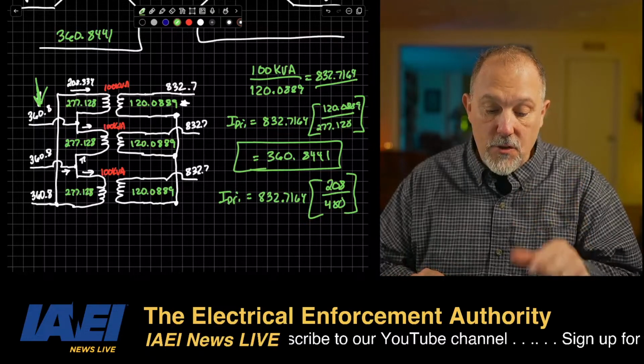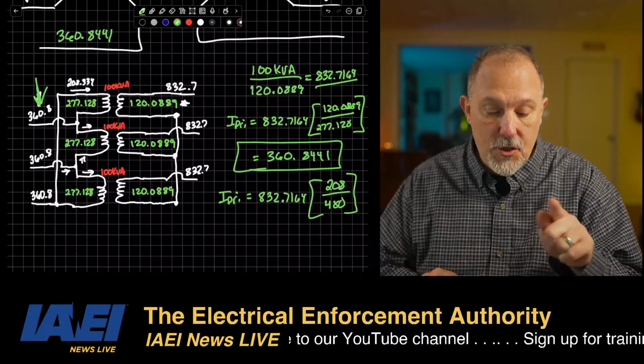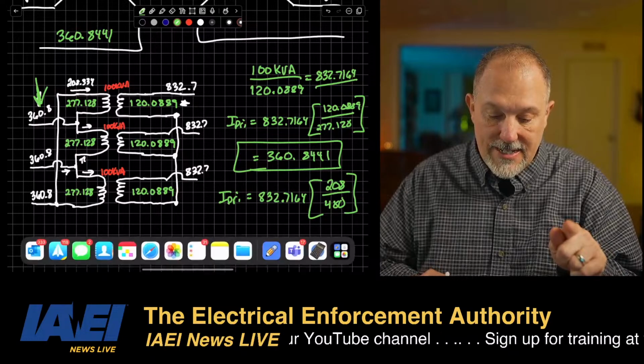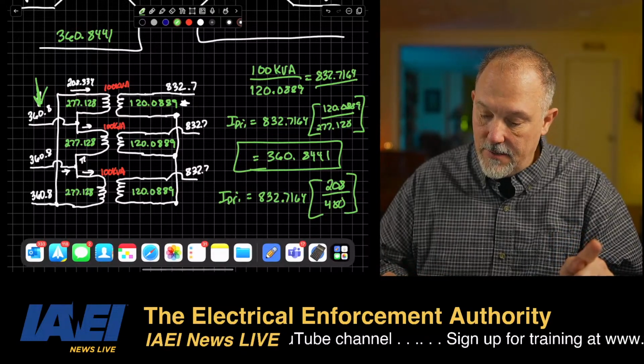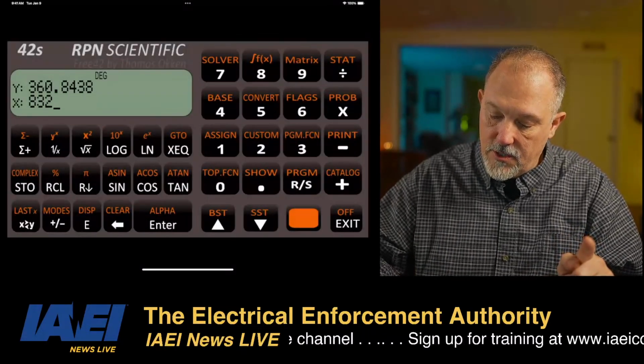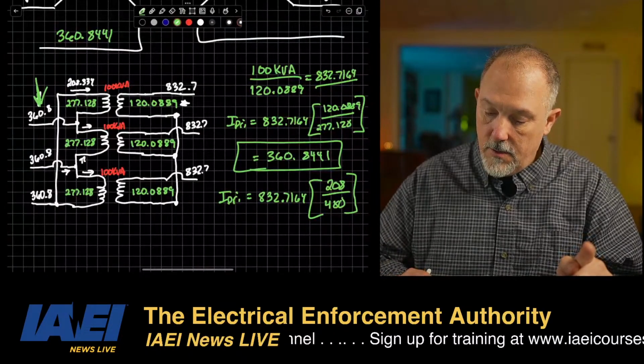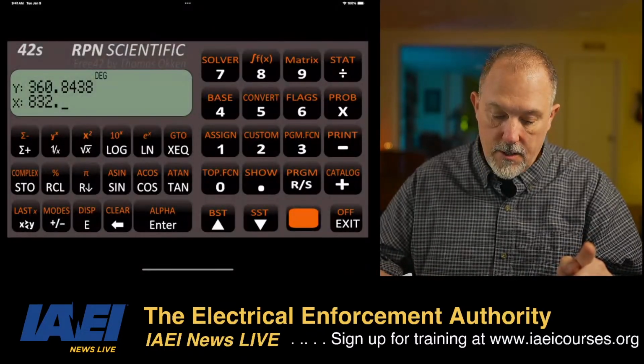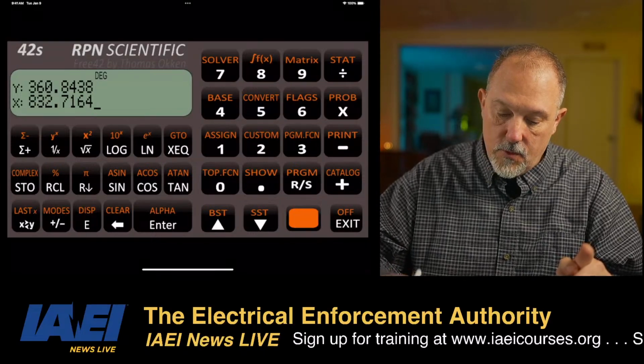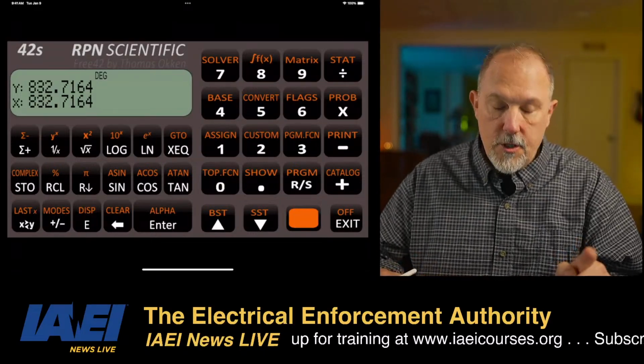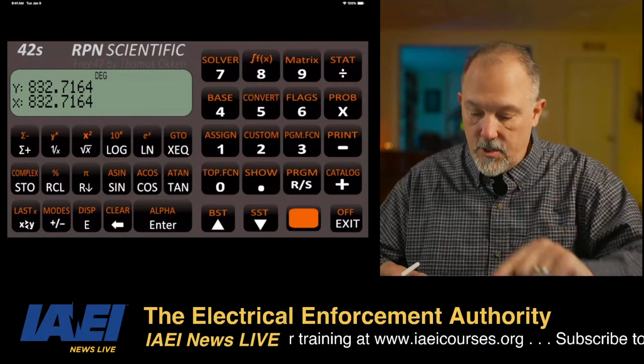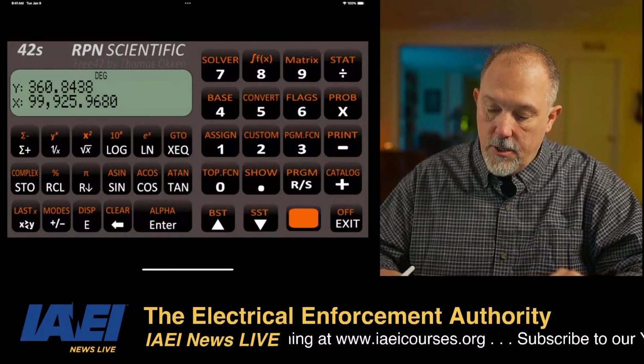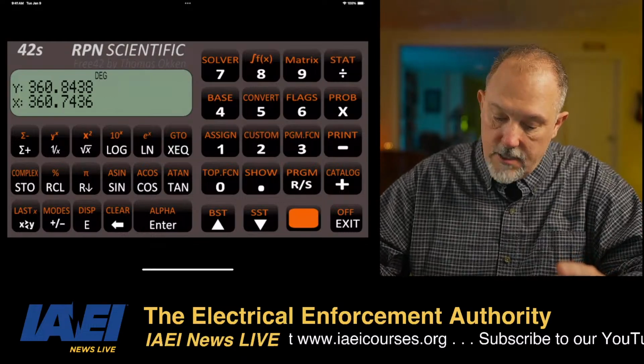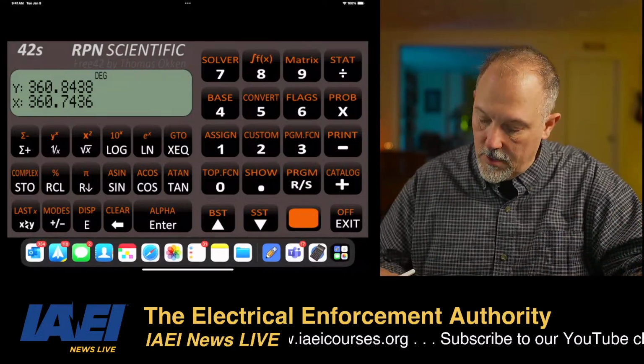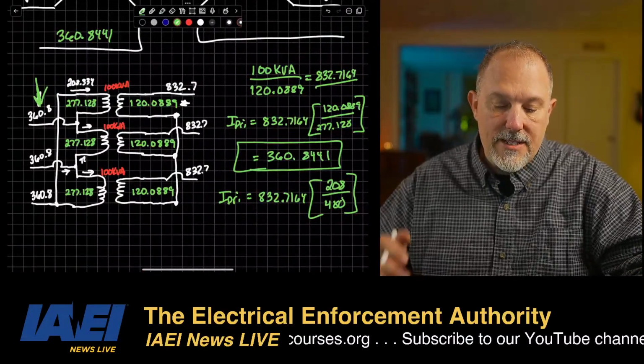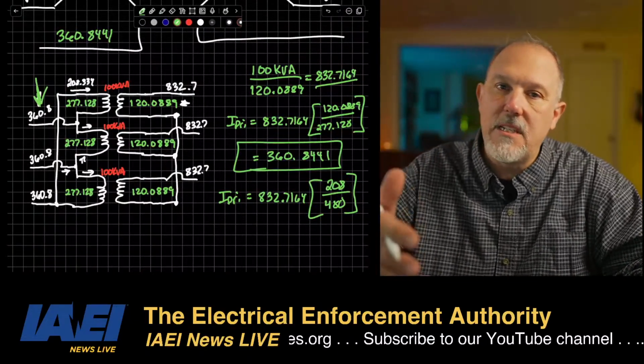Now, if I would have used 120 to 277, 832.7164, I'm going to use 120, 277, divide, 360.74. Now there's a difference. Instead of 360.84, it's 360.74.